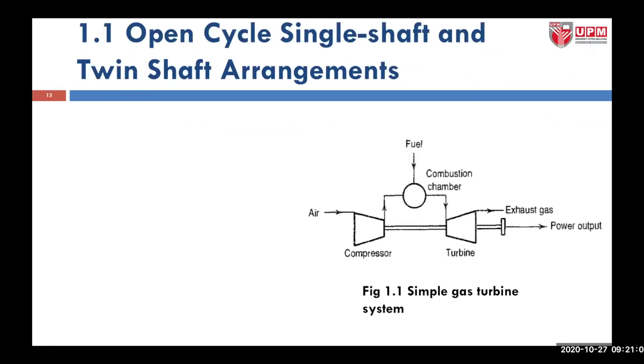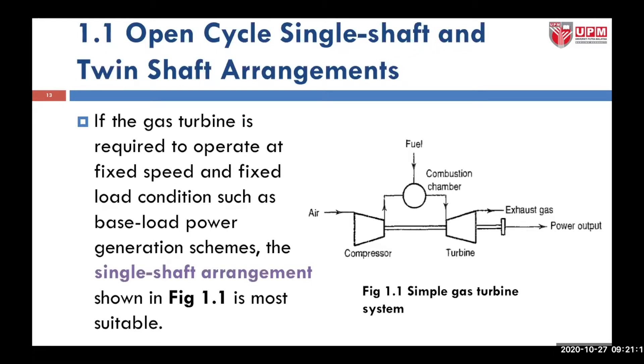This schematic, figure 1.1, shows a simple gas turbine system. If the gas turbine is required to operate at a fixed speed — you fix the speed and fix the load conditions such as a base load power generation scheme — the single shaft arrangement shown in figure 1.1 is more suitable. It is as simple as having a compressor connected via a shaft to the turbine, giving you the power output.